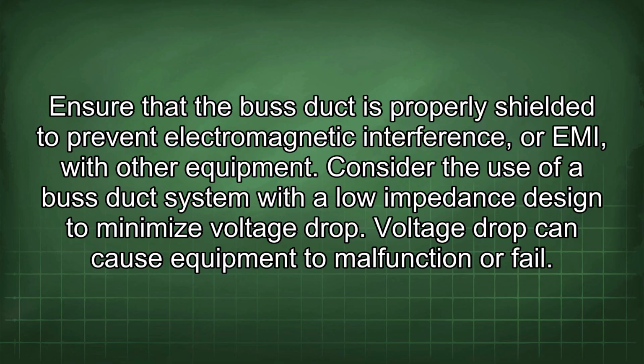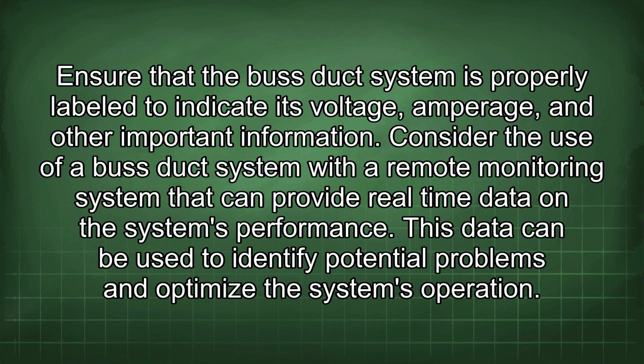Consider the use of a bus duct system with a low impedance designed to minimize voltage drop. Voltage drop can cause equipment to malfunction or fail. Ensure that the bus duct system is properly labeled to indicate its voltage, amperage, and other important information. Consider the use of a bus duct system with a remote monitoring system that can provide real-time data on the system's performance. This data can be used to identify potential problems and optimize the system's operation.